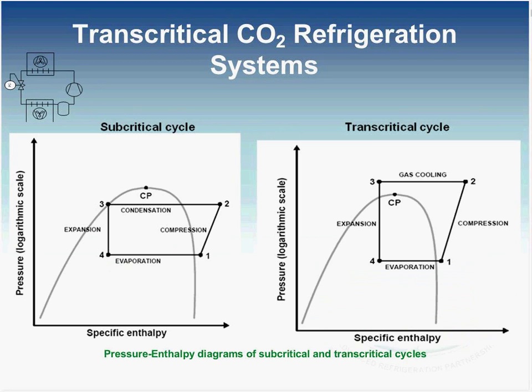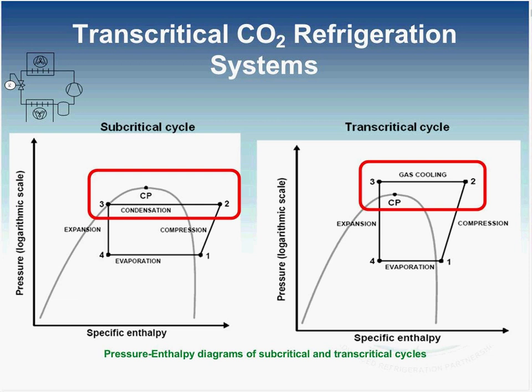So I talked a little bit about the difference in subcritical. I mentioned the words subcritical and transcritical earlier, and here are the two cycles on a pressure enthalpy curve, which is normally used in reviewing how these systems operate. On the left is a subcritical cycle, and again, it's what we've heard: CO2 used as a secondary refrigerant and CO2 used in a cascade arrangement. We basically operate the refrigerant below the critical point, which is indicated by the letters CP at the top of that curve. That means we can actually condense the refrigerant gas into a liquid and use it in a manner that's more traditionally seen in a vapor compression cycle in a supermarket. The right-hand side is a transcritical operation of the system.